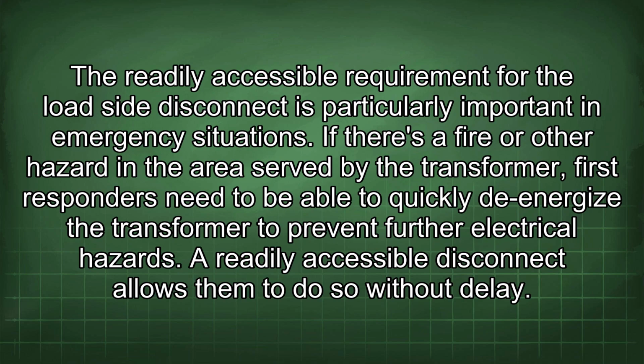The readily accessible requirement for the load-side disconnect is particularly important in emergency situations. If there's a fire or other hazard in the area served by the transformer, first responders need to be able to quickly de-energize the transformer to prevent further electrical hazards. A readily accessible disconnect allows them to do so without delay.